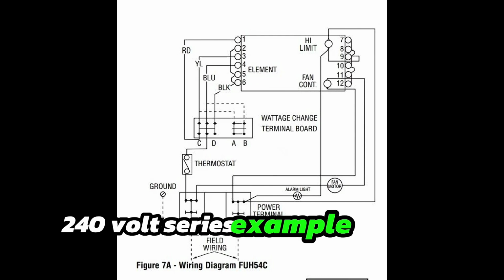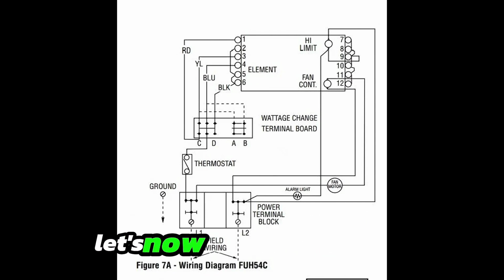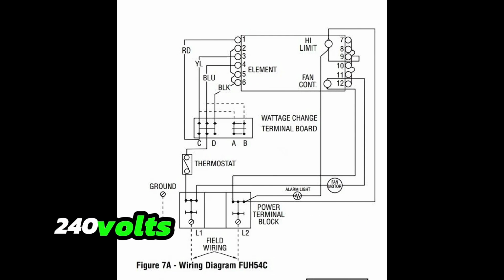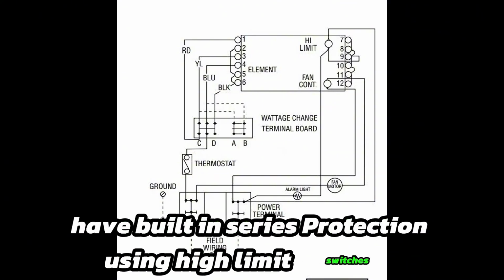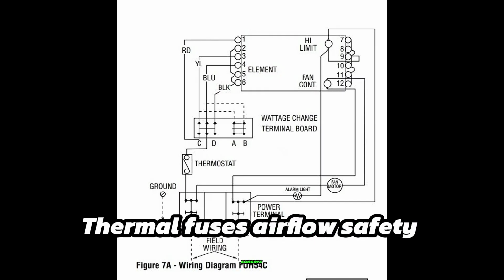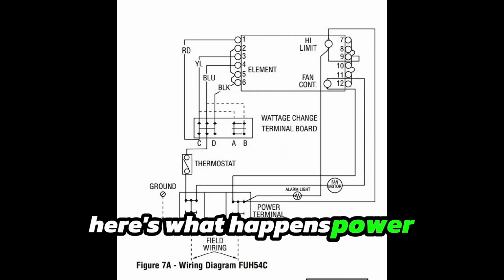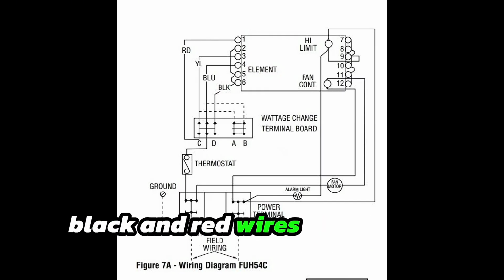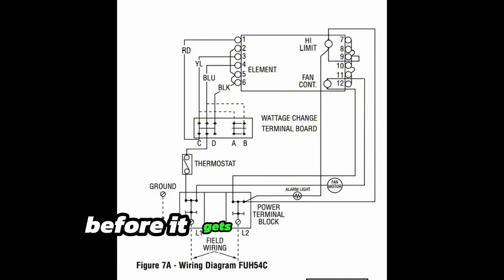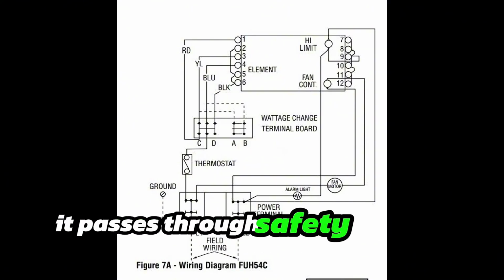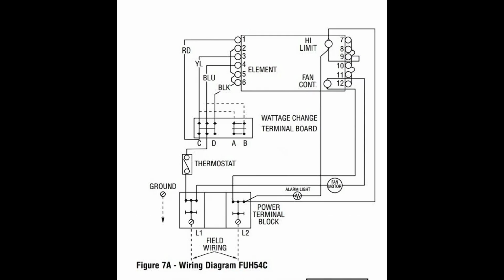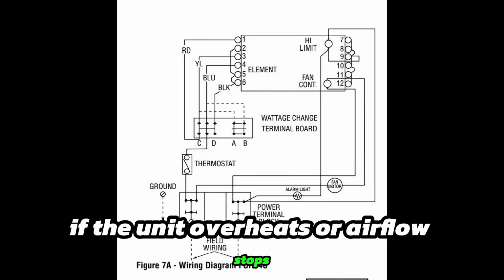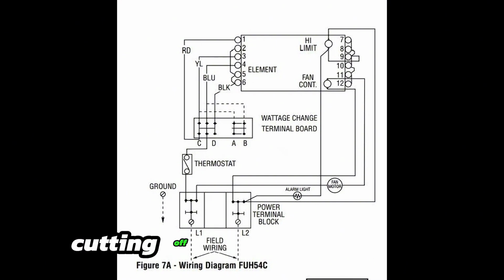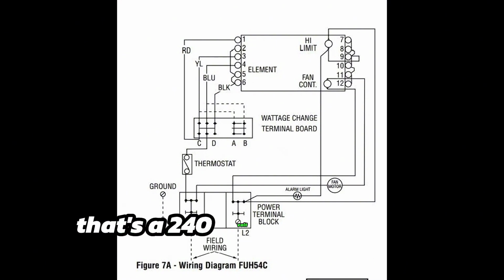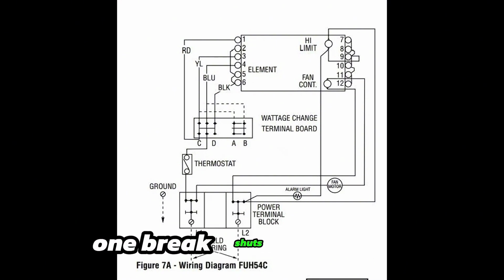240-volt series example, electric heater safety. Let's now talk high voltage, 240 volts. Electric heaters and air handlers have built-in series protection using high-limit switches, thermal fuses, and airflow safety sensors. Here's what happens. Power comes from the panel, black and red wires, and enters the heater kit. Before it gets to the heating elements, it passes through safety switches wired in series. If the unit overheats or airflow stops, any of those switches will open, cutting off power to the heater. That's a 240-volt series safety circuit. One break shuts it all down.